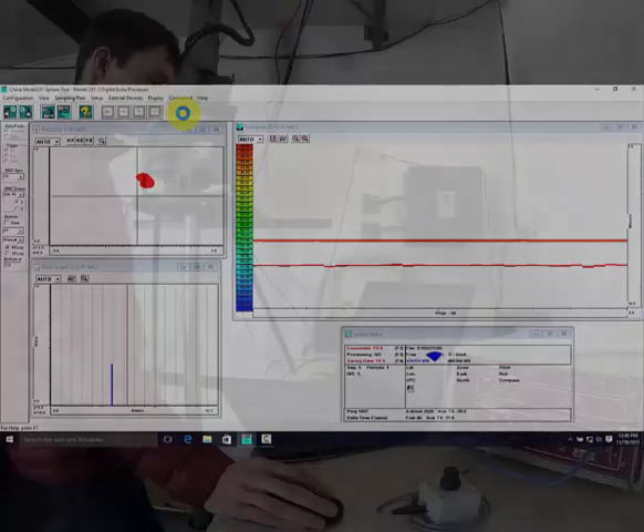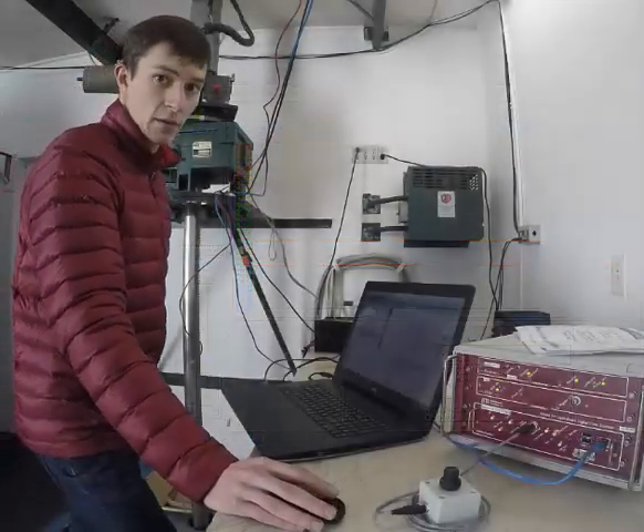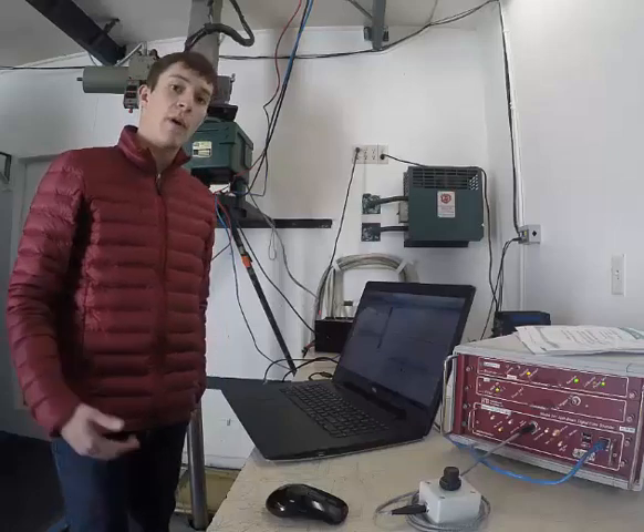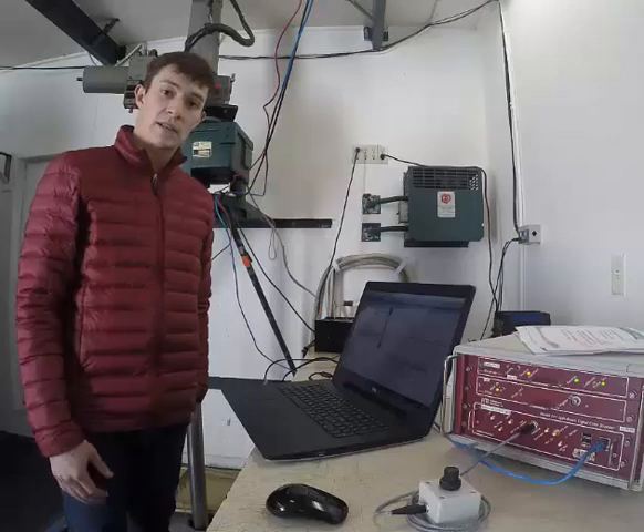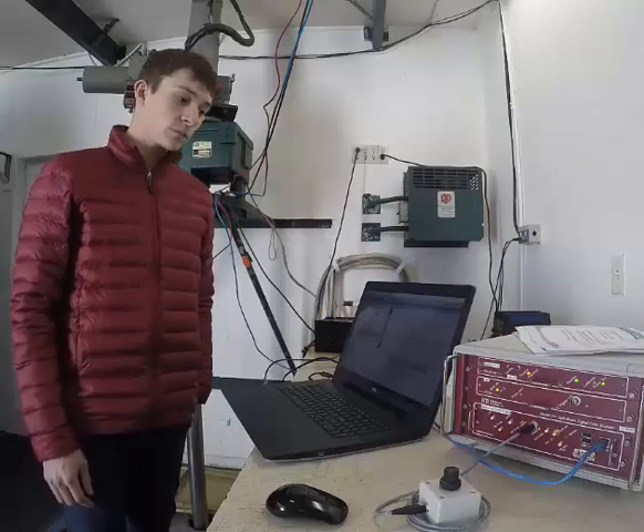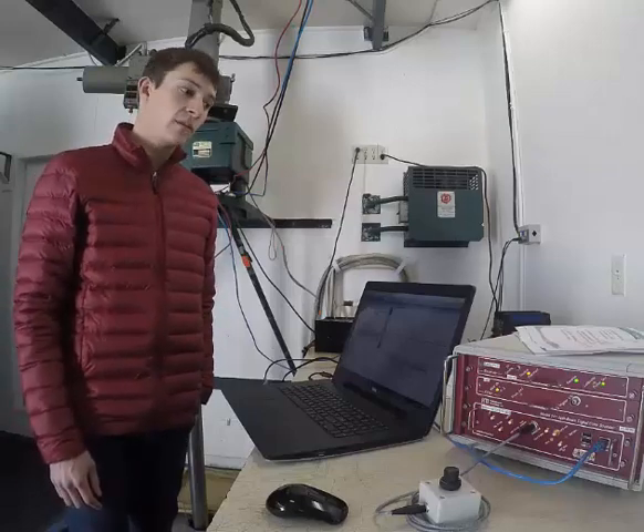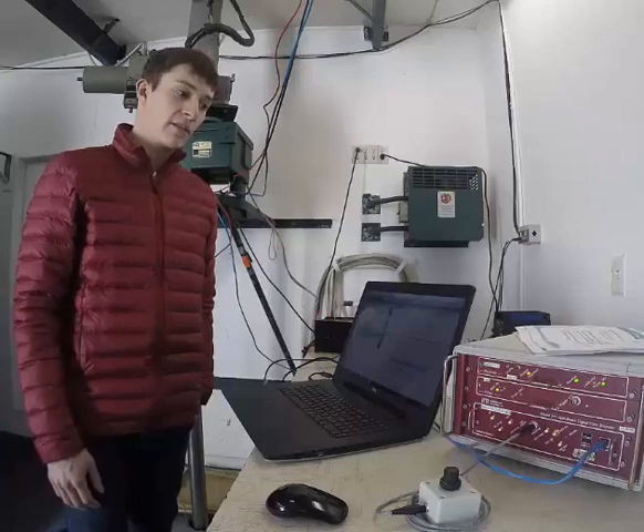After we've collected enough echoes, we can go back to command, stop processing, and when I do that, the software saves a .raw, a raw data file, which when we go back to the office, we can open up in Echoscape and run some statistics on our data and determine the transmit-receive sensitivity of the transducer.